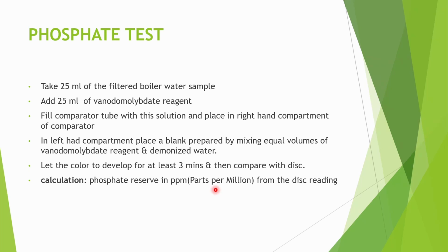So as boiler pressure or load increases with a consequent rise in the boiler tube wall temperature, sodium phosphate in the water in contact with the tube wall precipitates as crystals, causing the phosphate ion concentration in the boiler water to go down. Conversely, as the boiler load or pressure decreases, the precipitated crystals dissolve back into the boiler water, causing the phosphate ion concentration to rise. It is in such a mechanism that the phosphate ion concentration varies from time to time. So this is called the phosphate hideout phenomenon.